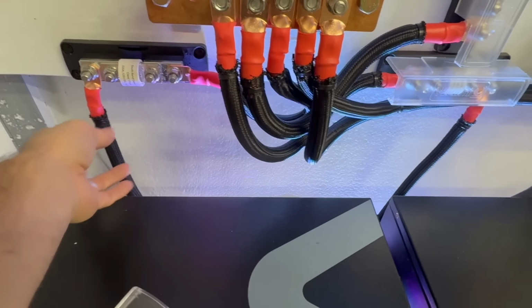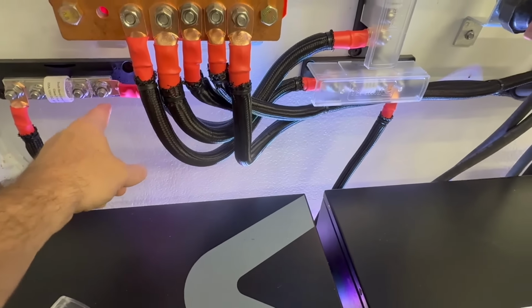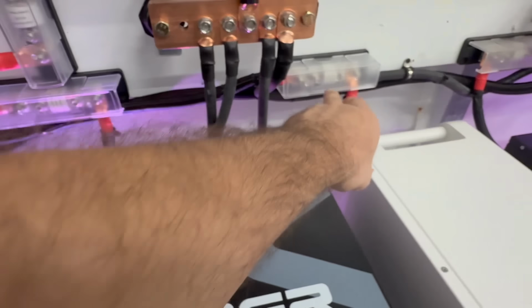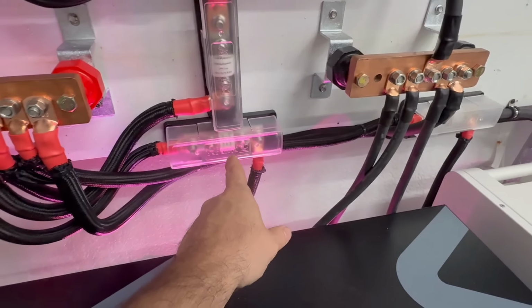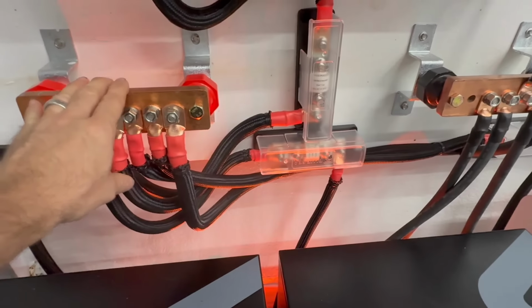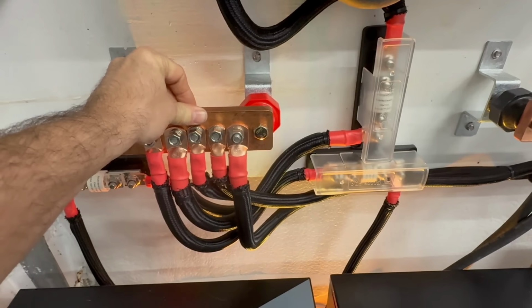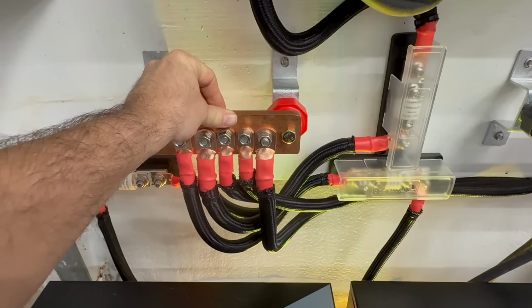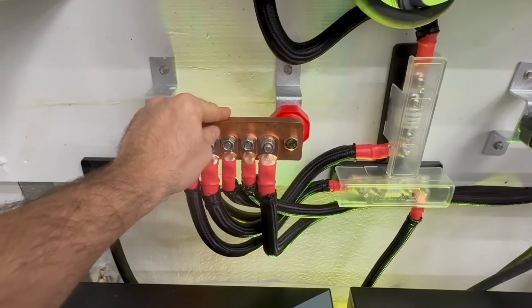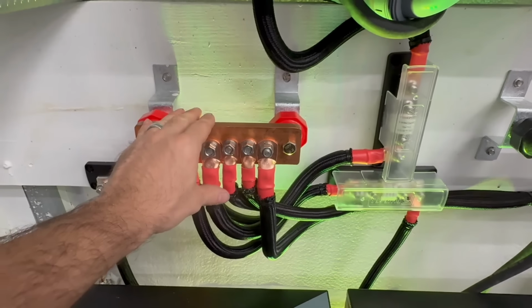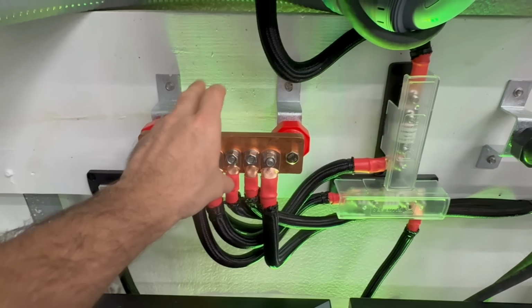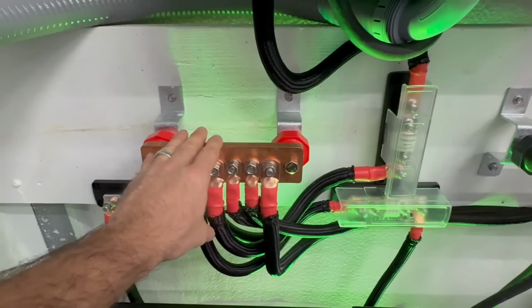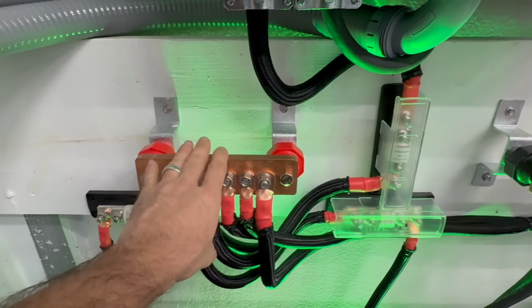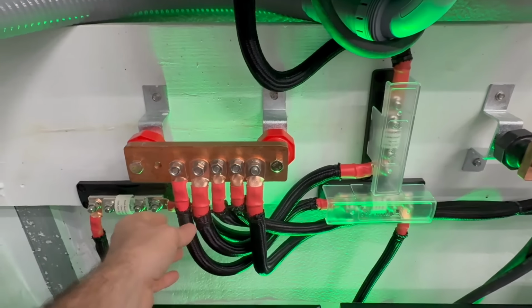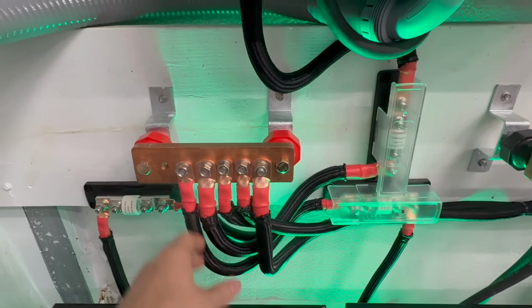So it goes up to the 2-aught cable, then to the T-class fuse for each of these three, and then into my bus bars. These can handle a tremendous amount of power, around 1,350 amps on the low side, at around 60 degrees Celsius. You could rate it higher, 1,500, 1,600, 1,700, whatever you need, but as you can see, all of this is overkill anyway.